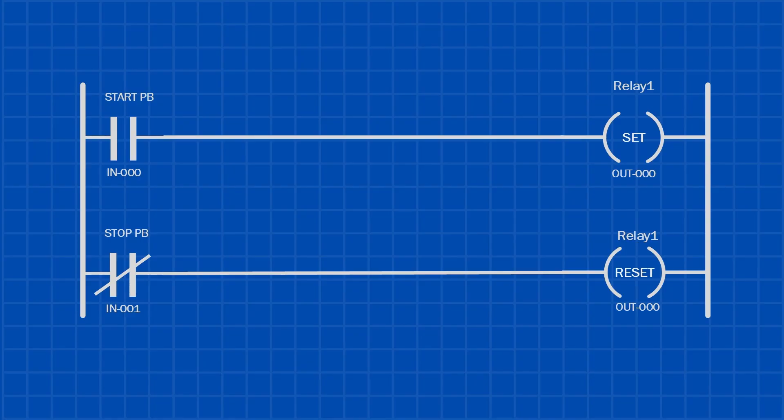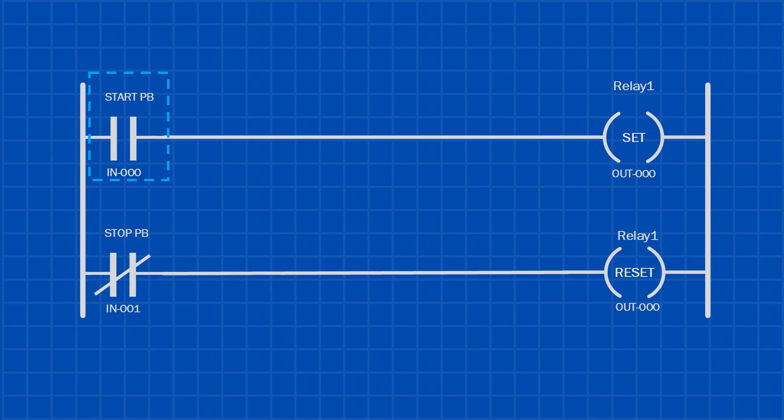Another way to create a latching circuit in a PLC is by using the set and reset instructions. When the start push button is pressed, relay one, or output 0-0-0, is set, which means it turns on and stays latched. Then, when the stop push button is pressed, the output is reset, and relay one turns off.